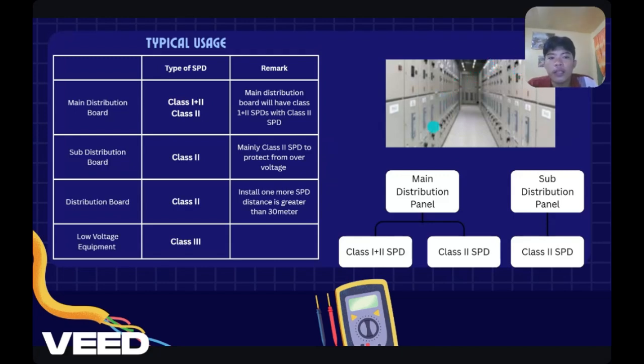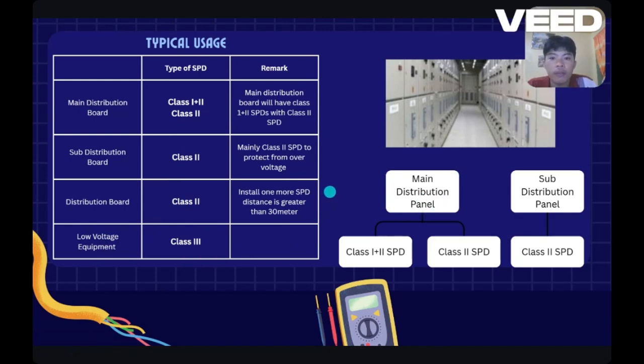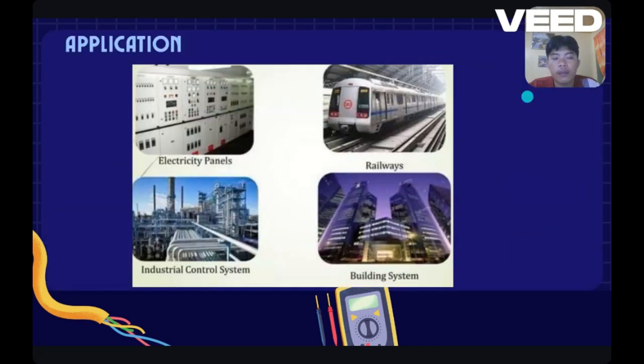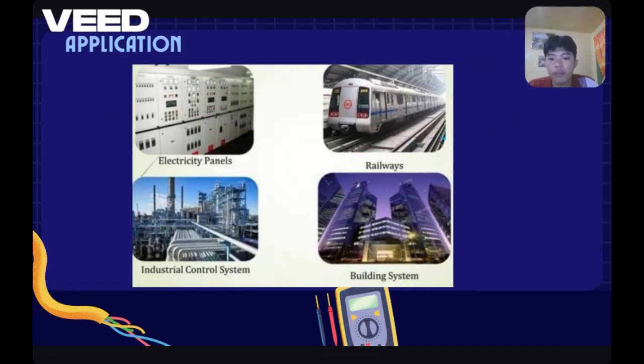So, typically usage. We have main distribution board, sub distribution board, and low voltage equipment. The main distribution board will have class 1 plus 2 SPD with class 2 SPD. Then in the sub distribution board, we mainly have class 2 SPD to protect from over voltage. Then at the distribution board, we install one more SPD if the distance is greater than 30 meters. In application, we have electricity panels, railways, industrial control systems, and building systems.